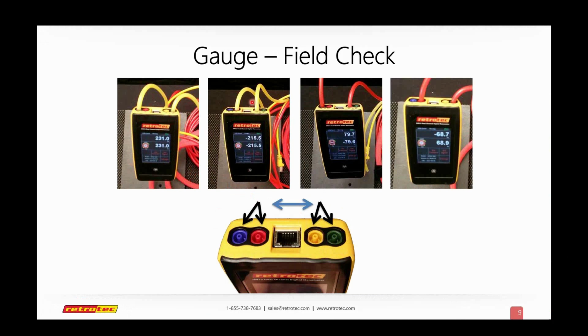And here you have a different configuration, where we're plugging into a different port, and so on. You'll notice that here we are testing our yellow cords, and here we're testing some blue or red cords. The point is that we're not only testing to make sure that our gauge is calibrated, or in calibration if you're a rater, but we're also making sure that our tubes don't have any holes, cuts, or any kind of problems. Any questions about that?